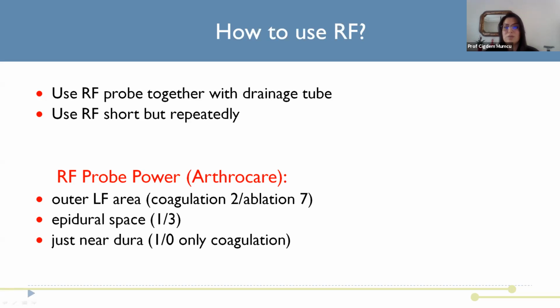What is the working principle of the RF device? Coagulation technology is a relatively new technology. It uses radiofrequency energy to excite the electrolytes in a conductive medium such as saline solution, creating energized plasma. This discharge plasma produces chemically active radical species, which break molecular bonds, causing tissue dissolution at low temperature, approximately 40 to 70 centigrade. That is the working principle of the RF device. We must use the RF probe with the drainage tube for heated fluid.